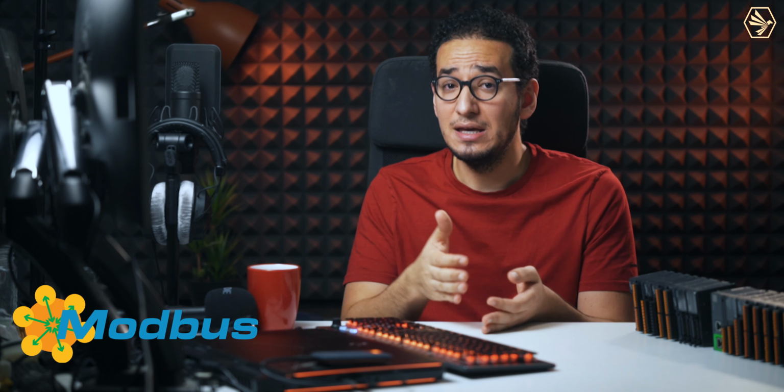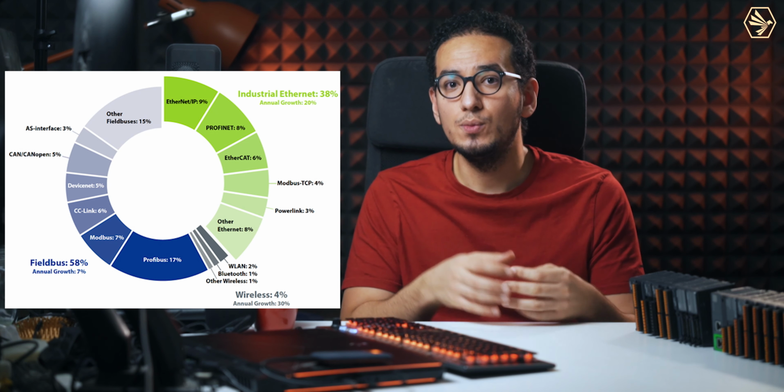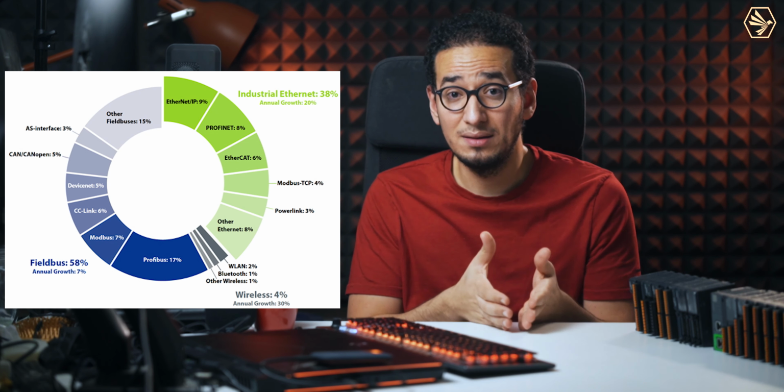Modbus is out since 1979 and it is the easiest protocol, which is very widely used in OEM panels, especially with the serial interface over the RS-232 or RS-485, which is well known as Modbus RTU. And with the rapid increase of industrial networks, we need to put that data on Ethernet. That's why we have gateways, which are simply serial to Ethernet converters.